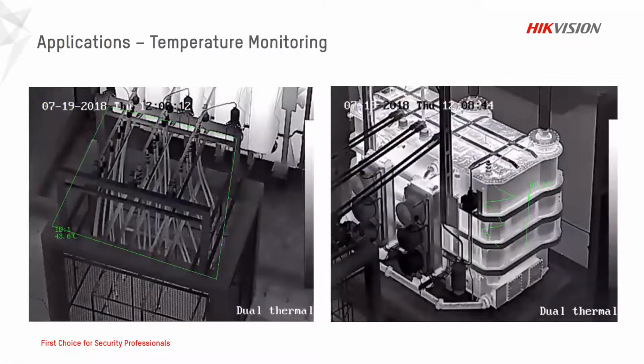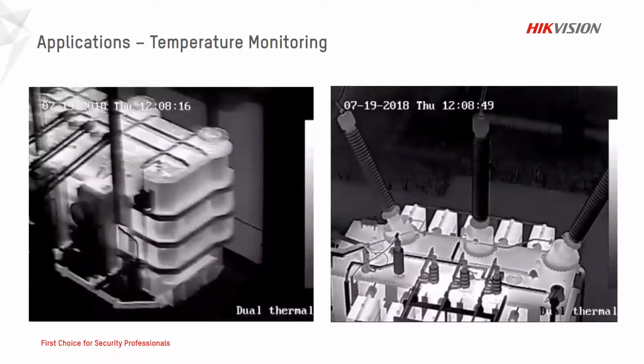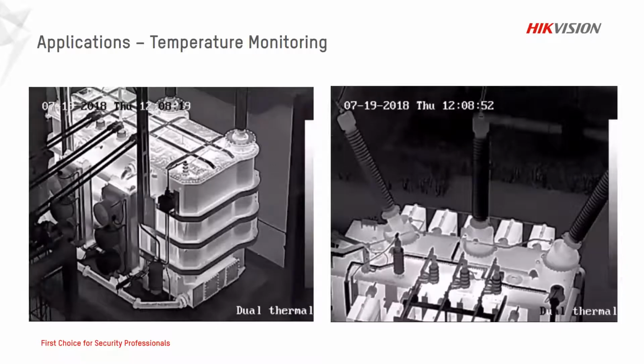And in general, temperature monitoring is a big point. It can be any kind of pump, engine, process control. You just put the camera there, and this example is from substation monitoring. They use a large PT camera, T version, and point it from one object to another. In every preset they have different measurement features and compare these temperatures to see quickly if there's some connector which, because of oxidation or something, is loosening and increasing the resistance.